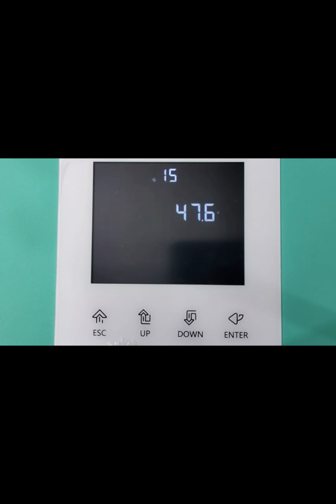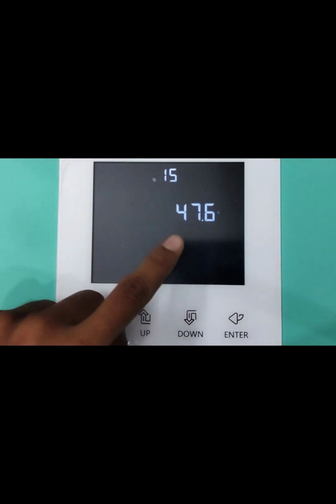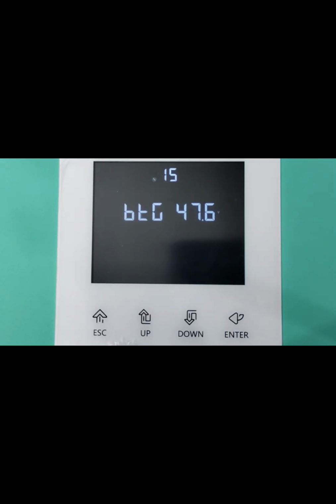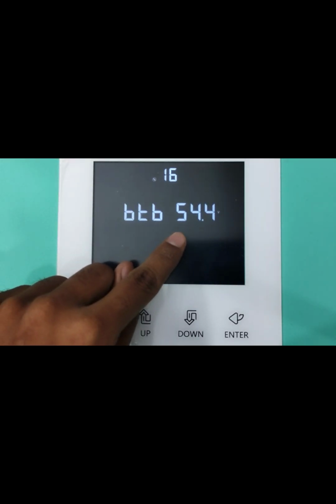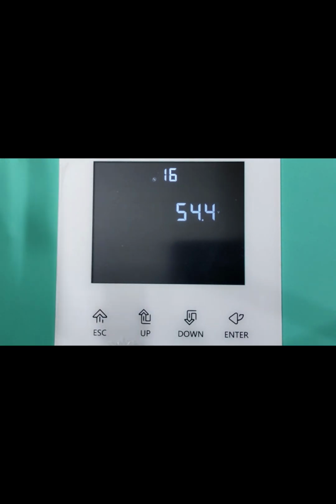Option 15, here we can set battery voltage points. We can also say this back to grid voltage. When the battery will reach at this point, the inverter will shift the load from battery to grid. Option 16, back to battery mode. When the battery will charge and reach certain voltage, the inverter will switch the load to the battery.